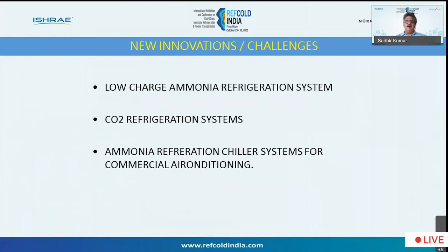And apart from that, what are the new innovations and challenges? We can think of low charge ammonia refrigeration systems. You can also think of air conditioning of the dairy being done using ammonia chilled water. We are doing this in many process halls, where we are using chilled water. And CO2 refrigeration systems, of course, may take more time. That is for some value-added products. If you want to keep them in a cold room, you can use CO2 systems also.